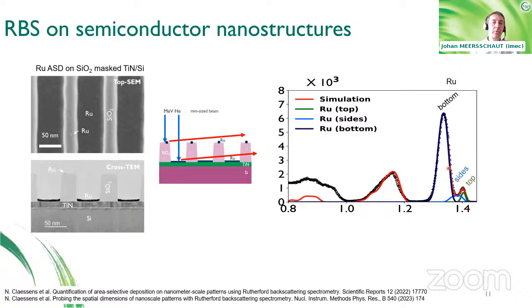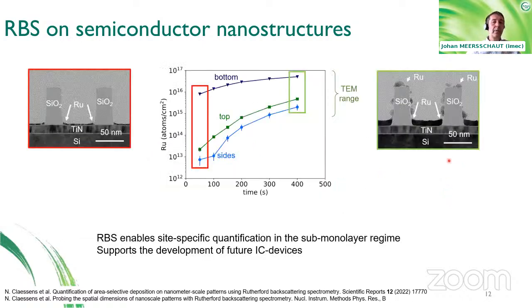You see that it is composed of a signal at a lower energy, which stems from this ruthenium signal, which is coming from the bottom of the fins. And besides that, you also have a signal from the top. So by quantifying these amounts, the contributions of the three areas, we can quantify the areal density for the sides, the top and the bottom. You can see that there is a lot of ruthenium at the bottom, while there is less ruthenium deposited on the top and on the sides.